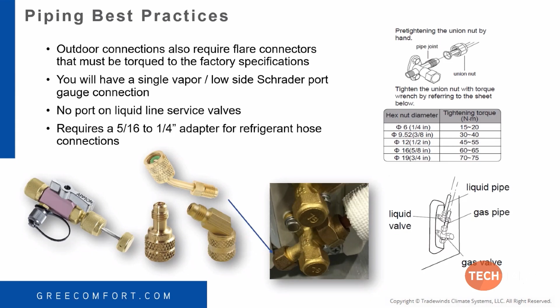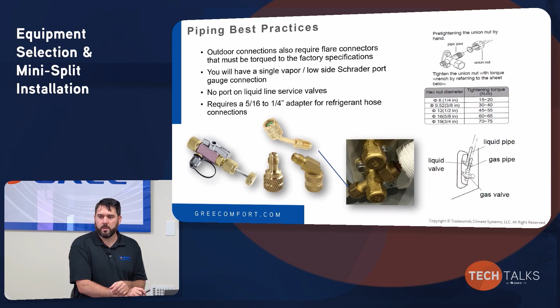You have a single vapor low side Schrader port gauge connection for your service hoses on the outdoor units. Why do we not have a liquid port, Greg? That's a good question. I mean, they're both on the same side of the system, though. So in cooling mode, they're both low side. In heating mode, they're both high side.